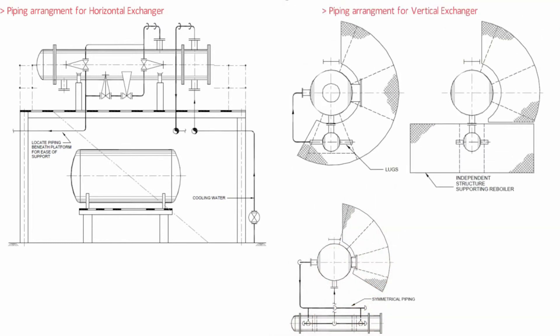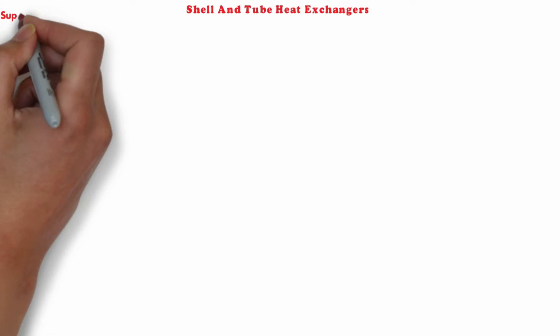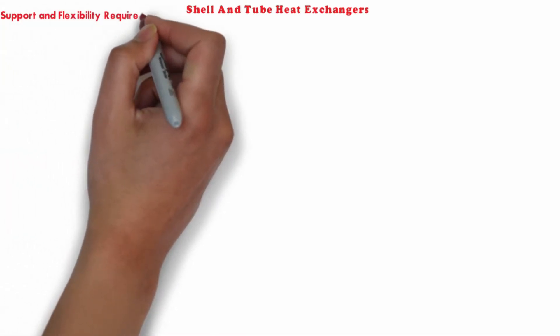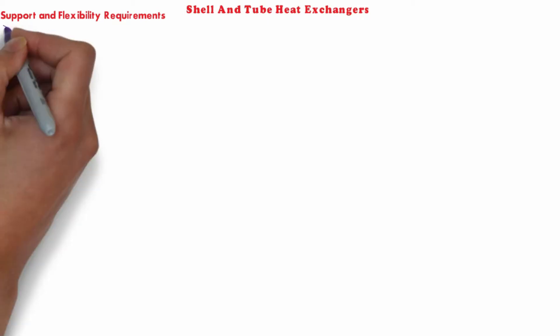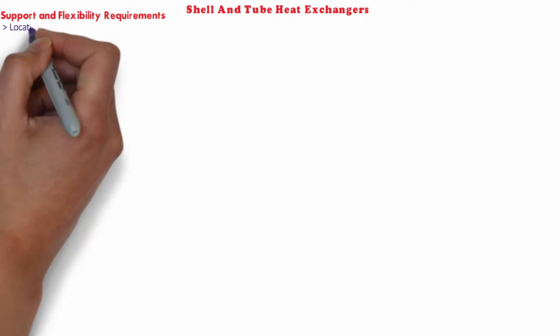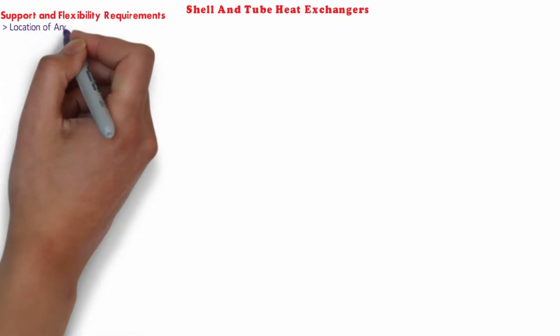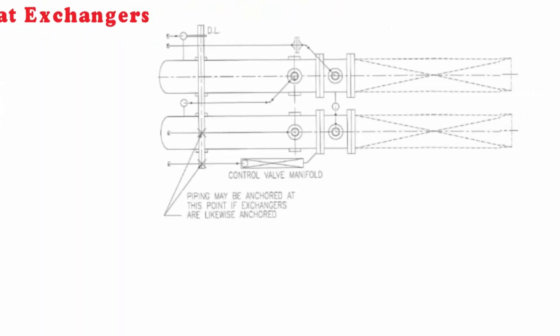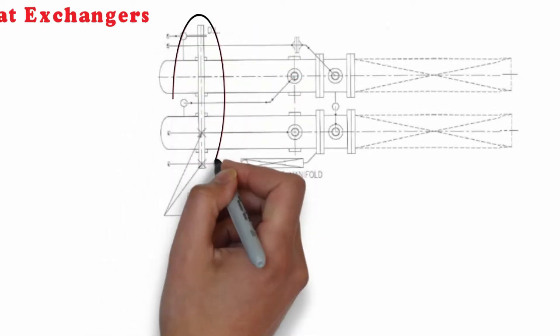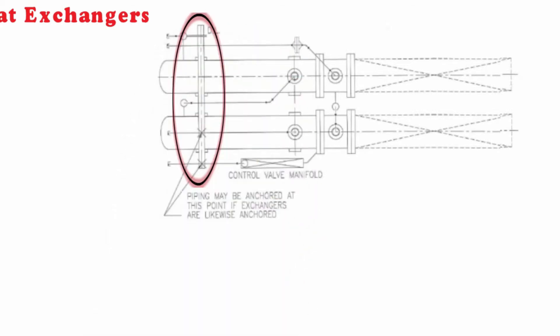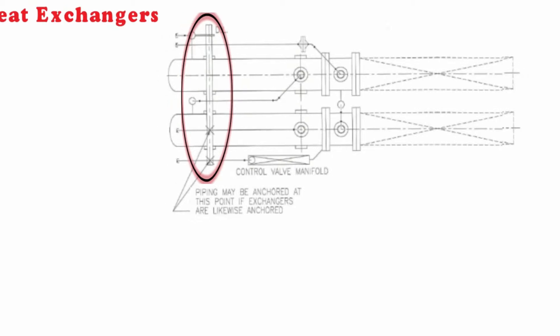Now let's talk about support location and the flexibility requirement for heat exchangers. General points should be taken care of while deciding the support location. Anchors play a large role in determining the piping configuration for exchangers. It should be considered that in many cases, the location of anchors can be adjusted to accommodate a better piping design. This is applicable to both pipe anchors and exchange support anchors. Stress group recommendations should be followed to ensure minimum piping loads on nozzles of heat exchangers.